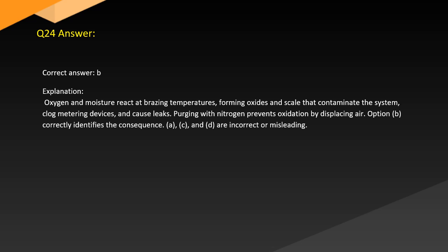Answer. Correct answer. B. Explanation. Oxygen and moisture react at brazing temperatures, forming oxides and scale that contaminate the system, clog metering devices, and cause leaks. Purging with nitrogen prevents oxidation by displacing air. Option B correctly identifies the consequence. A, C, and D are incorrect or misleading.